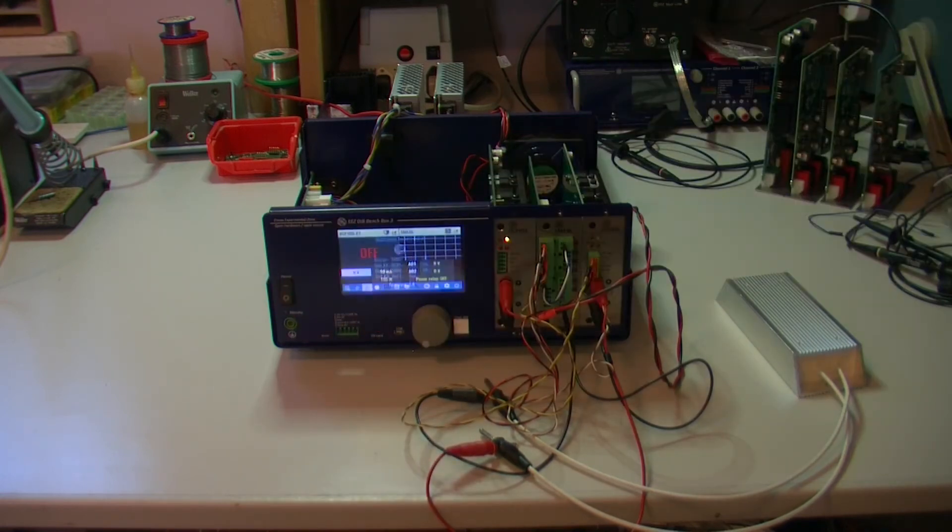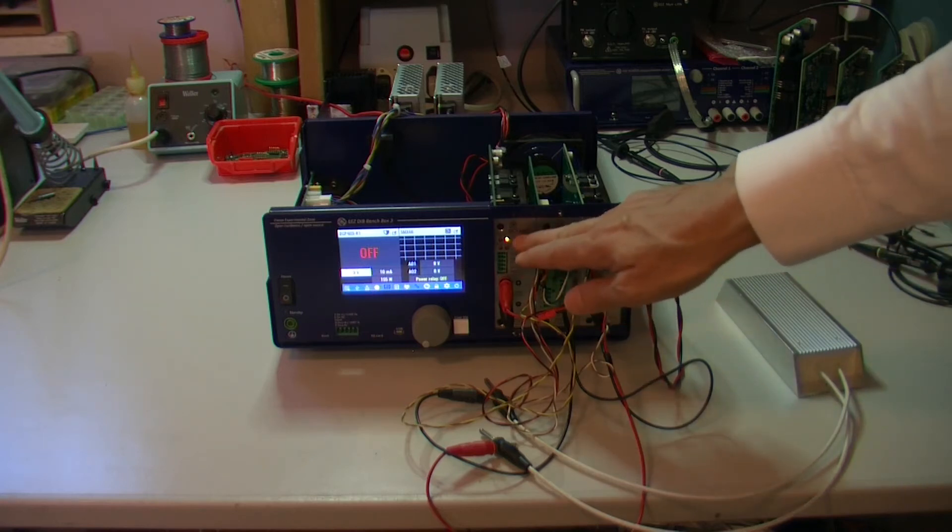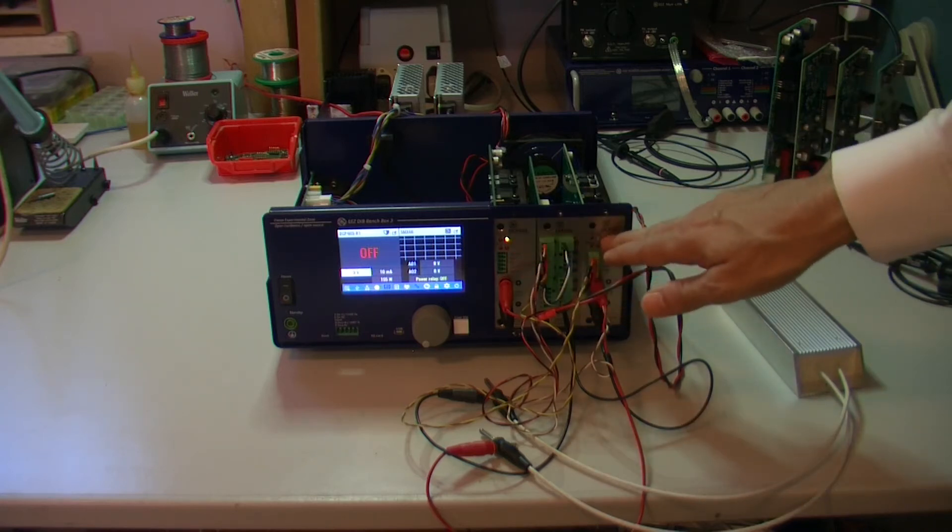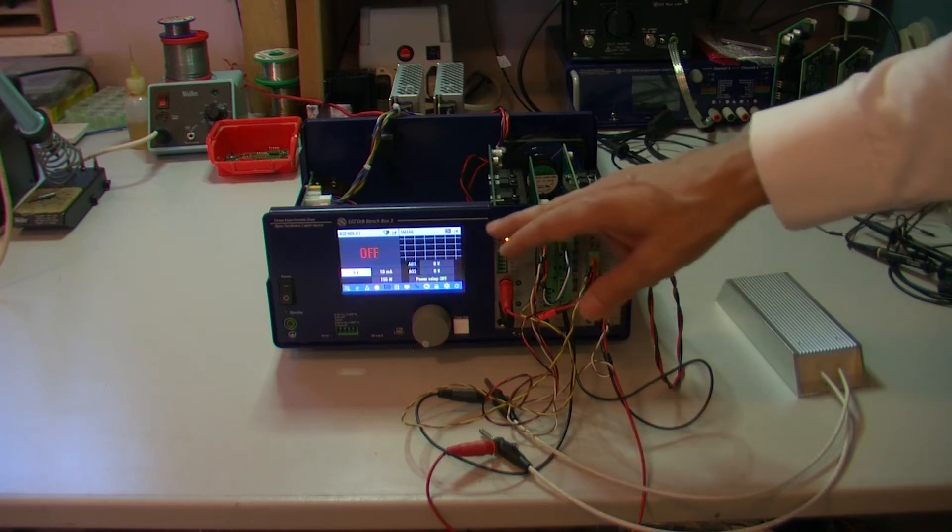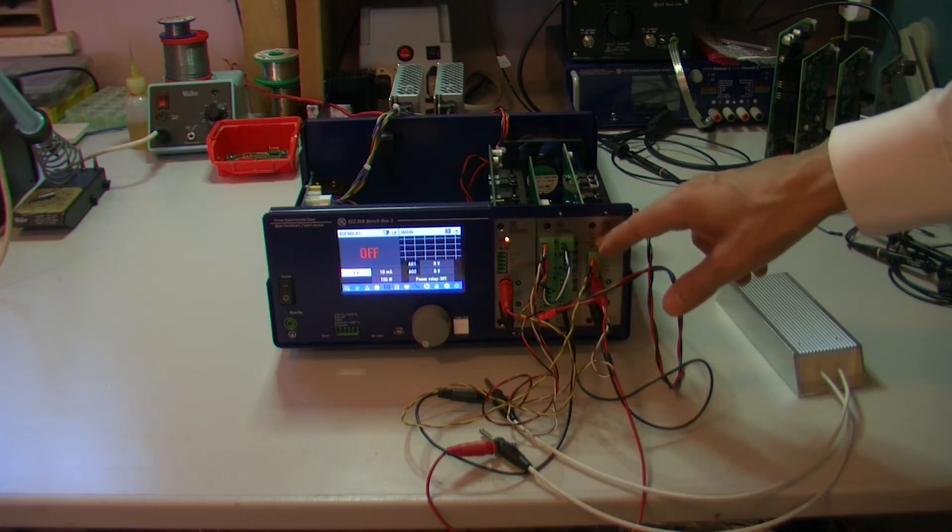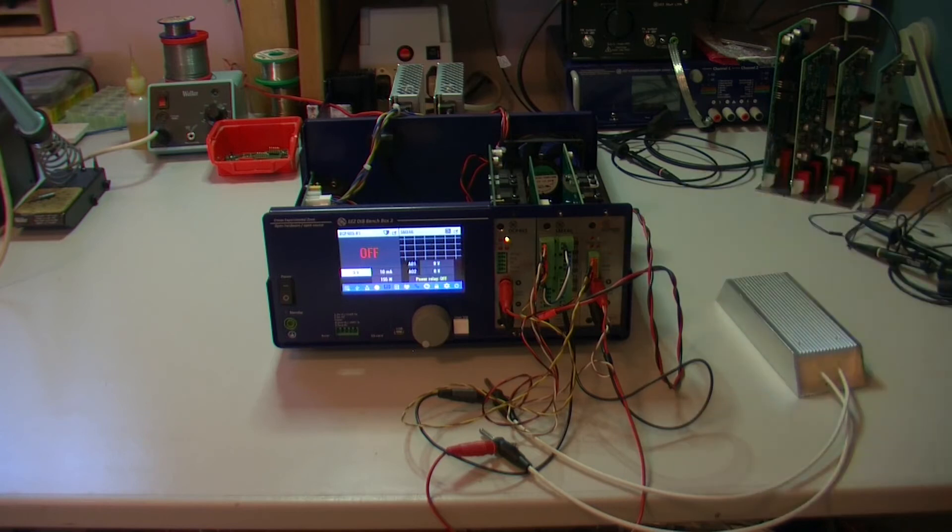it will recognize just those two modules. First two because this one is still new and it's not initialized and BB3 doesn't know what is on that third slot. So that will be the part of testing procedure to initialize the module to continue to work with it.